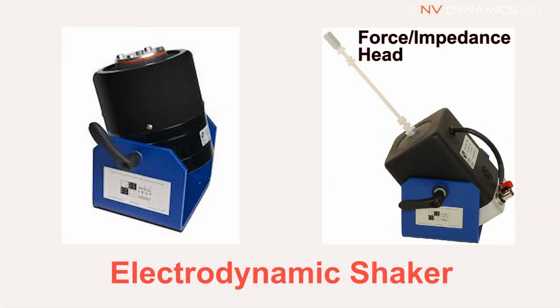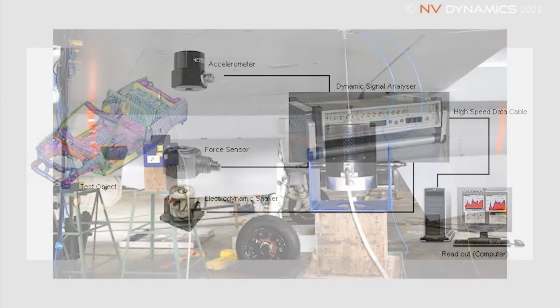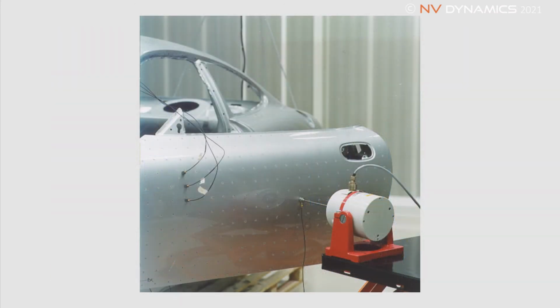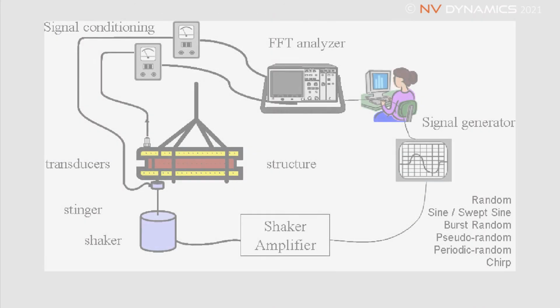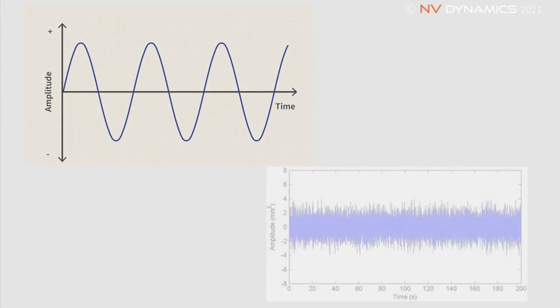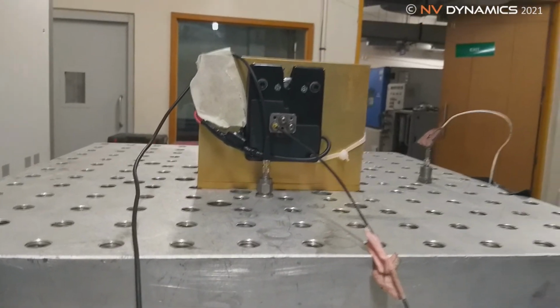The other common method of system response testing is using small force shakers that are coupled to the system under test via force transducers as the interface. One or more such electrodynamic shakers are used depending on the size of the test object and its configuration. The drive force is introduced through a connected amplifier which excites the system under test using various types of sources like sine, random and their combination. The responses are gathered using accelerometers or other vibration sensing devices.